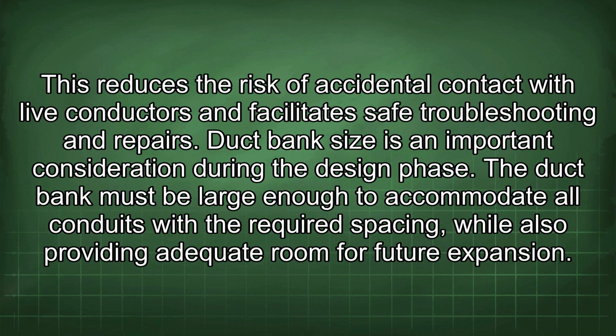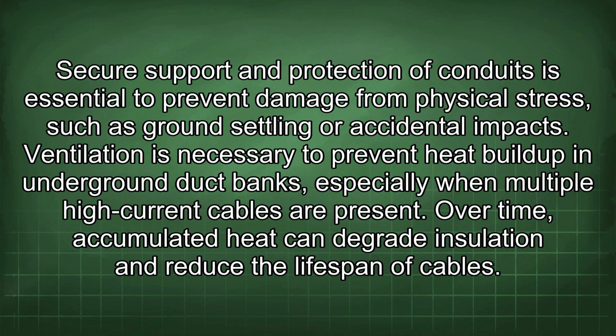Duct bank size is an important consideration during the design phase. The duct bank must be large enough to accommodate all conduits with the required spacing, while also providing adequate room for future expansion. Secure support and protection of conduits is essential to prevent damage from physical stress such as ground settling or accidental impacts. Ventilation is necessary to prevent heat buildup in underground duct banks, especially when multiple high-current cables are present. Over time, accumulated heat can degrade insulation and reduce the lifespan of cables.